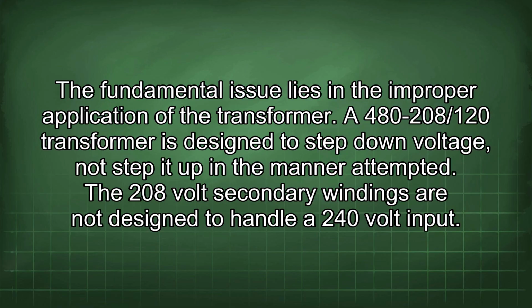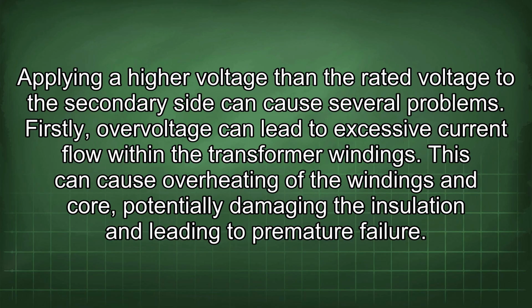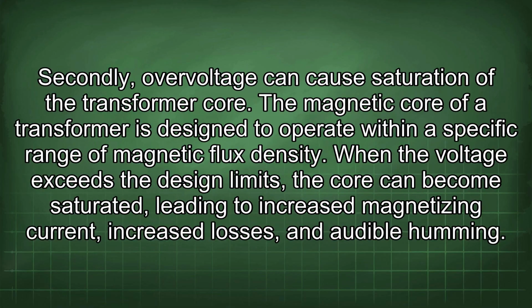The 208-volt secondary windings are not designed to handle a 240-volt input. Applying a higher voltage than the rated voltage to the secondary side can cause several problems. Firstly, overvoltage can lead to excessive current flow within the transformer windings. This can cause overheating of the windings and core, potentially damaging the insulation and leading to premature failure. Secondly, overvoltage can cause saturation of the transformer core.